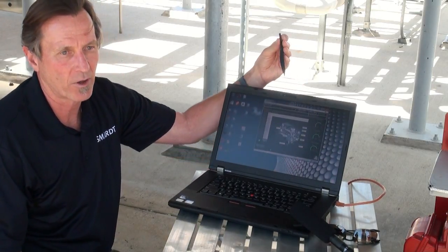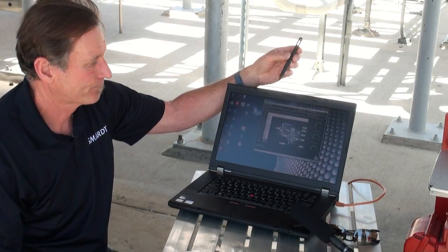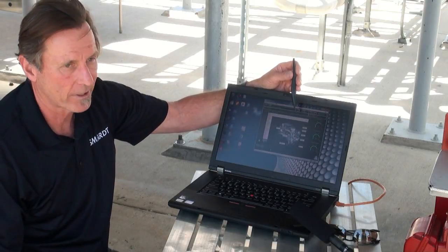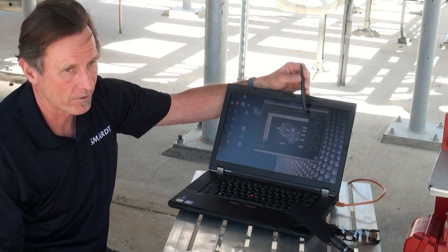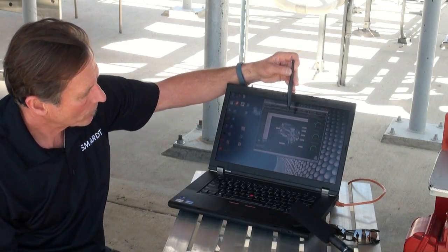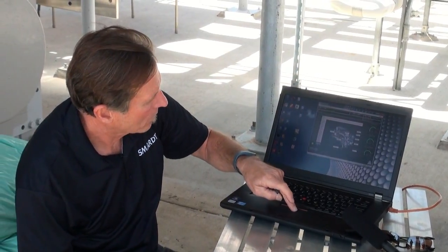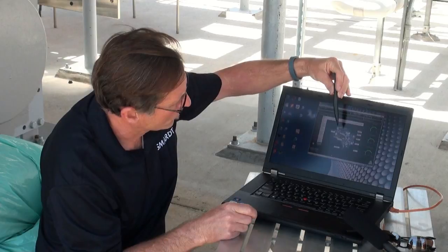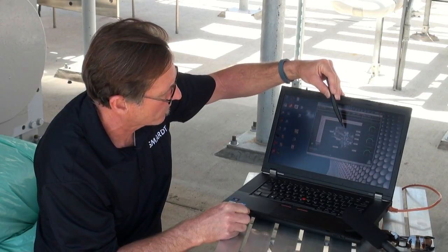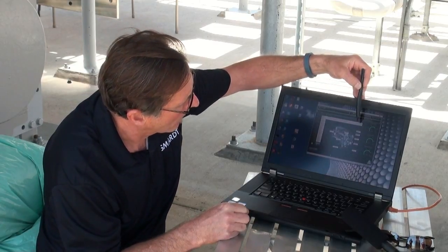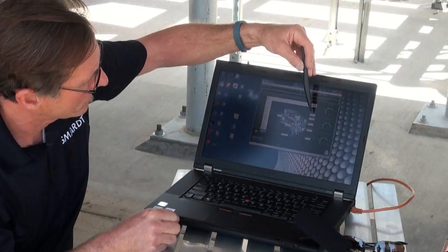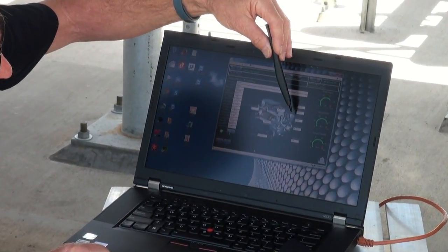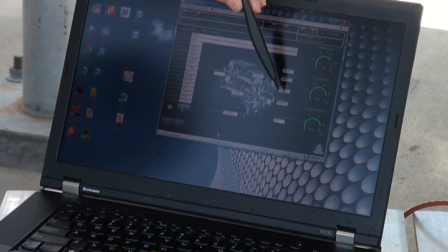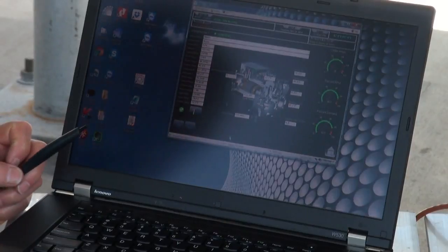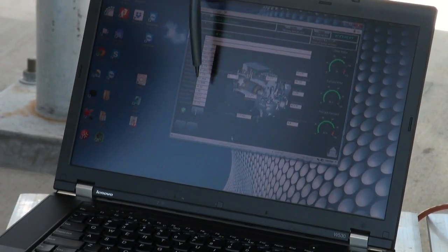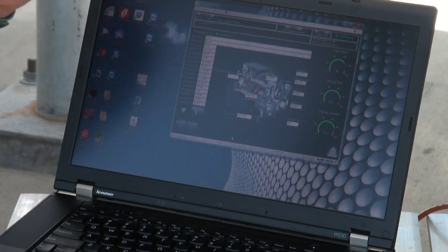But there's two different levels. You've got the alarm level, and then you have the critical fault level. And that's where you'll actually shut down, in the critical fault. And there's a number of alarm points and critical fault points. In fact, they all have alarm points and critical fault points. But that's what you want to look for. Those are two indicators that you want to keep an eye on: motor temperature and inverter temperature. You've got discharge superheat, saturated discharge temperature, then suction superheat, then saturated suction temperature. So you've got quite a bit more information here. You've got compressor hours displayed here as well.